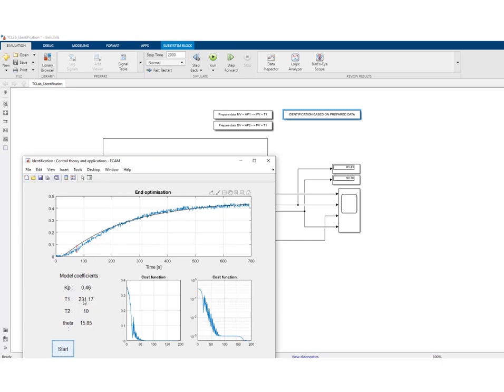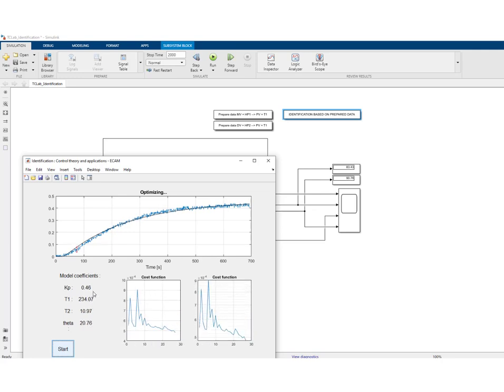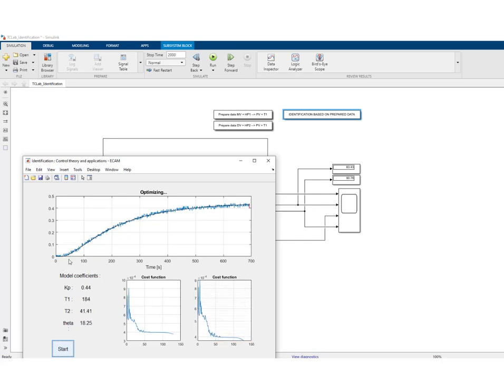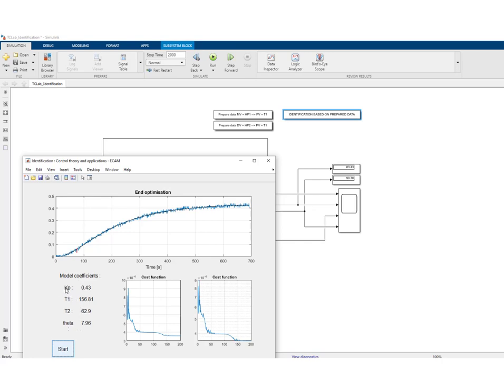The optimization routine is fitting the output of the model — in black — to the experimental data by adapting the parameters of the Van der Grinten model: the gain, the two lag time constants, and the delay. After one run we are not entirely satisfied, so we continue the optimization from the obtained parameters. The optimization is doing better and better, and we are satisfied with the fit. These are the parameters of our Van der Grinten model: two time constants and a delay identified from the second experiment, yielding a model of the disturbance dynamics.